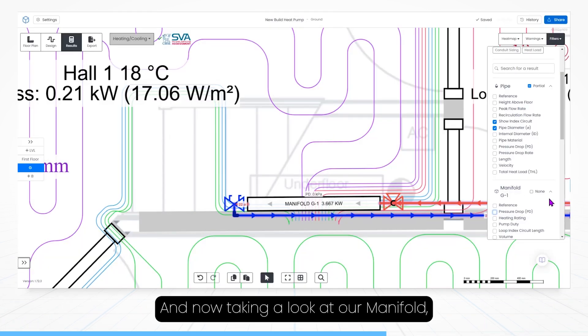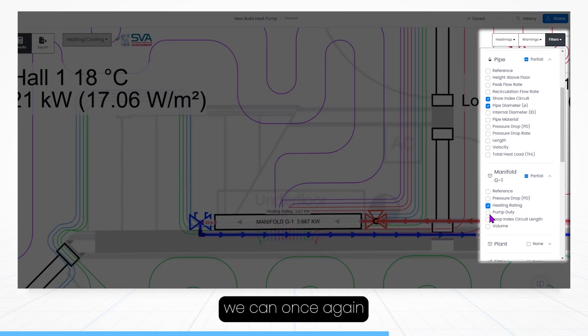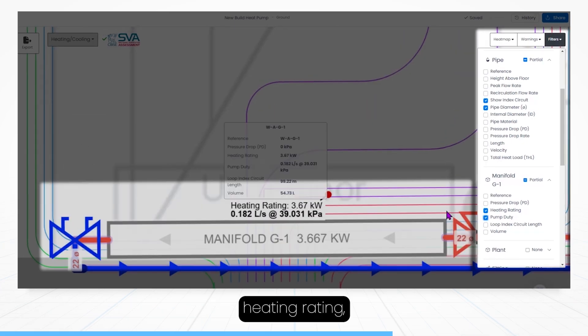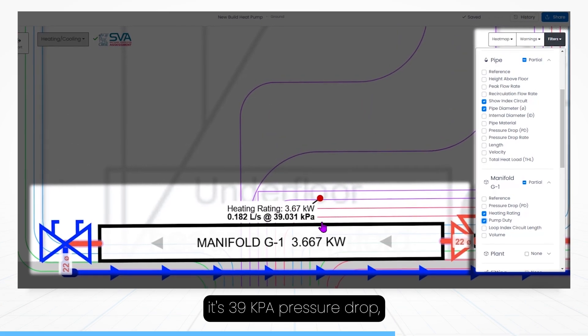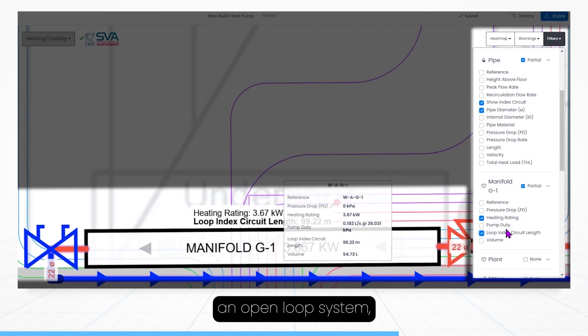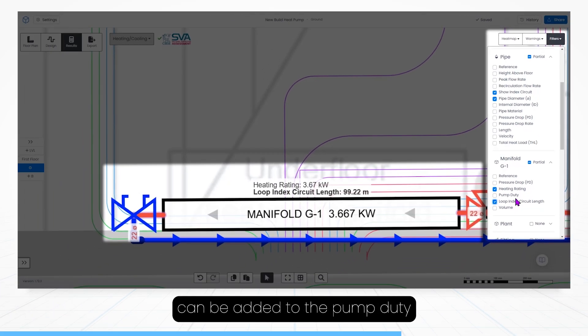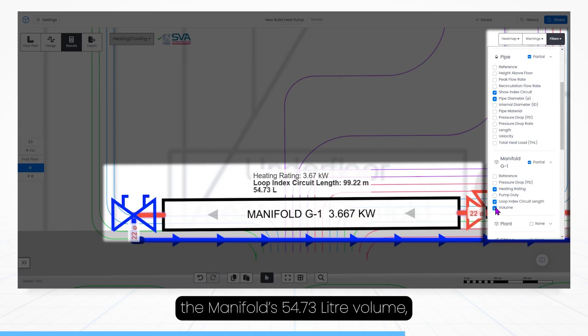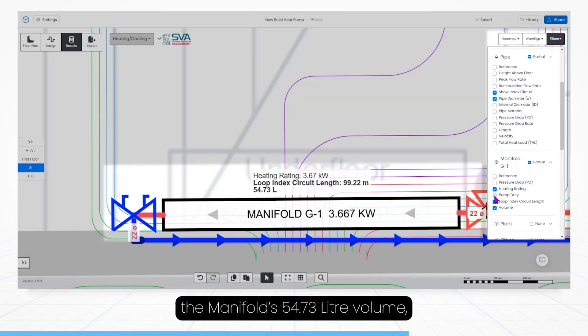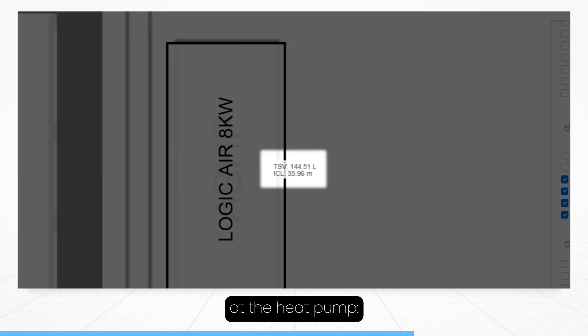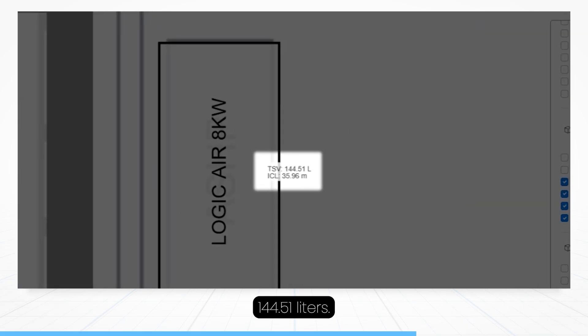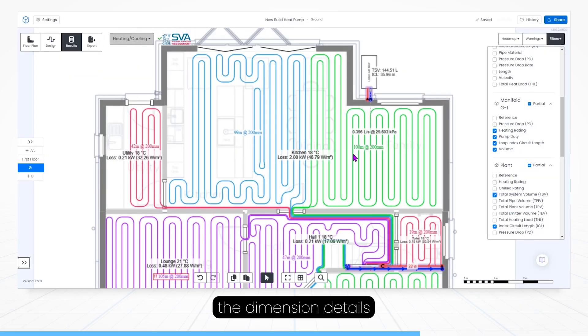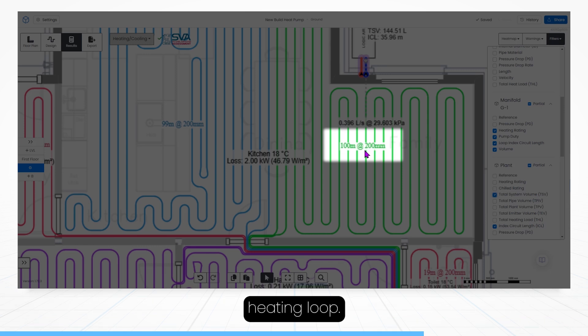And now taking a look at our manifold, we can once again see the pump duty, we can see the manifold's heating rating, its 39 kPa pressure drop, which if you're designing an open loop system, can be added to the pump duty at the heat pump. And finally, we can also see the manifold's 54.73L volume, which contributes to the total system volume, which is shown at the heat pump, 144.51L. And of course, you can find the dimension details for each underfloor heating loop.